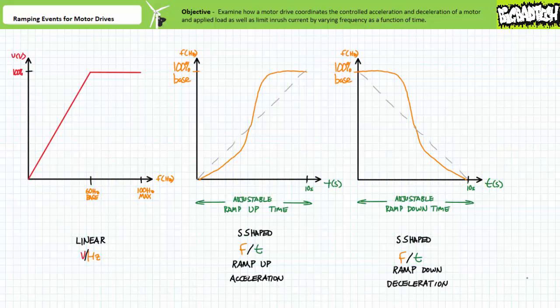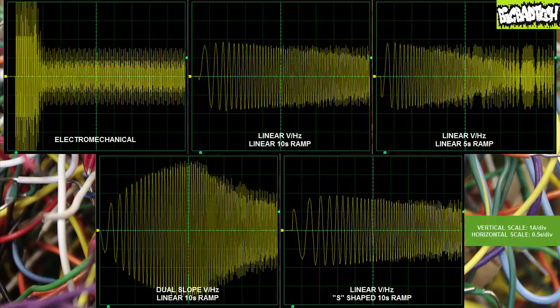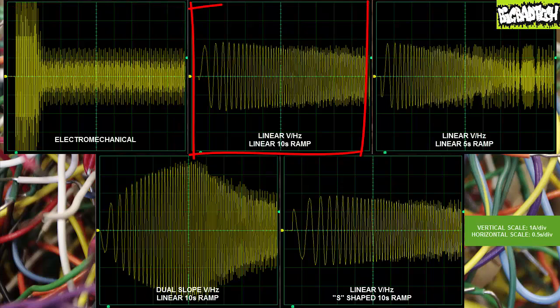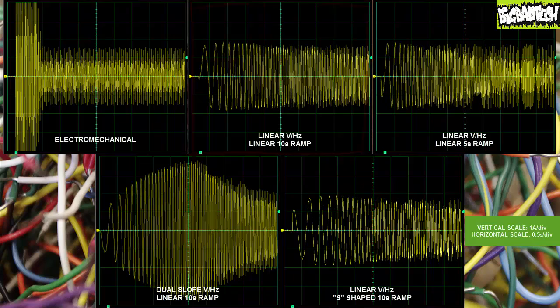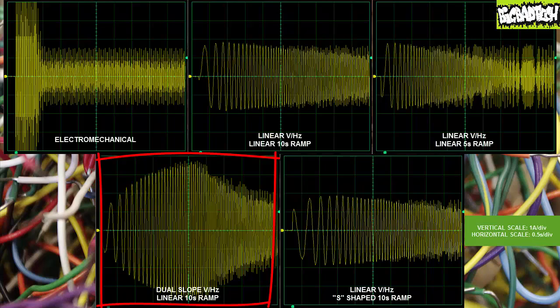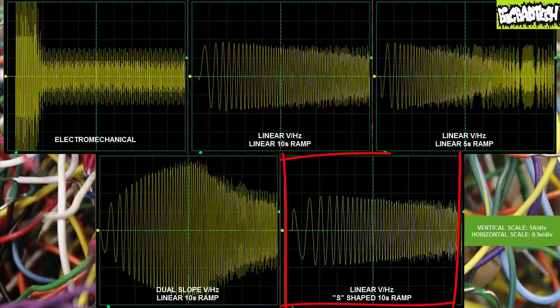That's about it for acceleration and deceleration ramping events for motor drives. In closing, I present all five plots of line current for the different starting methods for your consideration. One: an old-school electromechanical across-the-line full-voltage starter exhibiting constant frequency and massive inrush. Two: a motor drive with a linear volts per hertz profile and a linear 10-second ramp-up time, exhibiting controlled current at a steadily increasing frequency and a substantially gentler rate of acceleration. Three: a motor drive with a linear volts per hertz profile with a shorter linear 5-second ramp-up time, exhibiting a more aggressive yet still manageable rate of acceleration. Four: a motor drive with a dual-slope torque boost volts per hertz profile and a linear 10-second ramp-up time, exhibiting a notable current boost at low speeds designed to break the static friction of a heavy load at rest. And finally, five: a motor drive with a linear volts per hertz profile and an S-shaped 10-second ramp-up time, exhibiting controlled current and a slower initial rate of frequency increase followed by a more aggressive increase as the acceleration event unfolds.